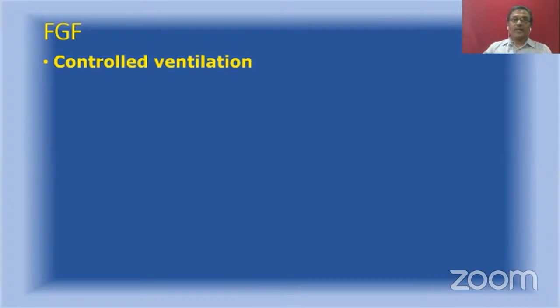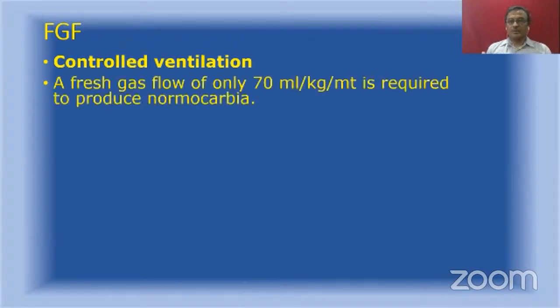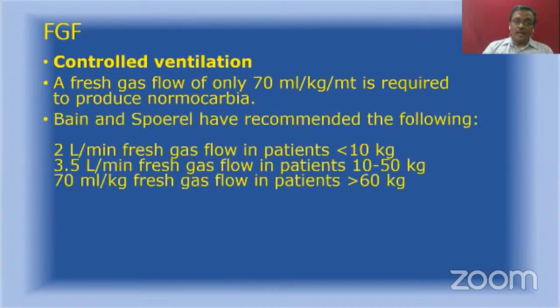Now, let us see the fresh gas flow requirement for Bain circuit. The Bain circuit is best for control ventilation. It is not an ideal circuit for spontaneously breathing patient. The fresh gas flow requirement is about 70 to 100 ml per kilogram per minute. And this was the recommendation of Bain and Spoerel, but nowadays nobody is using Bain circuit for children less than 20 kg. So the take-home message is, for an adult, you can use 70 ml per kilogram per minute. The minimum flow to be used with a Bain circuit is around 3 to 3.5 liters. You should not reduce the flow less than that.